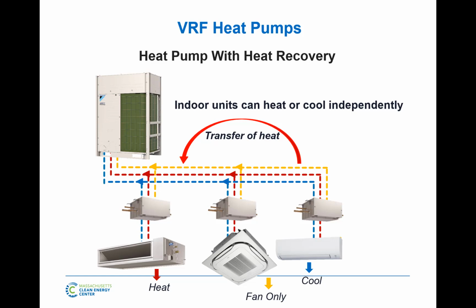Because A, you got to add changeover devices, you got to add piping, whether it's a 2-pipe or a 3-pipe system, it overall adds some piping. The machines, too, have more technology in them. To the naked eye, they'll look the same. A 10-ton heat pump VRV or a 10-ton heat recovery VRV will look the same to you on the roof, unless you look at the model numbers. You open it up, though, there's more reversing valves, there's more things going on in there, so there's a cost difference there. The fan coils are the same. A 2-ton ducted fan coil that's tied to a heat pump or heat recovery system doesn't matter. That fan coil is the exact same.